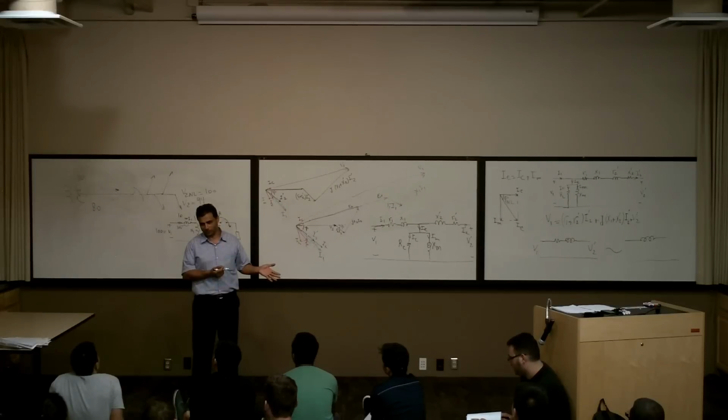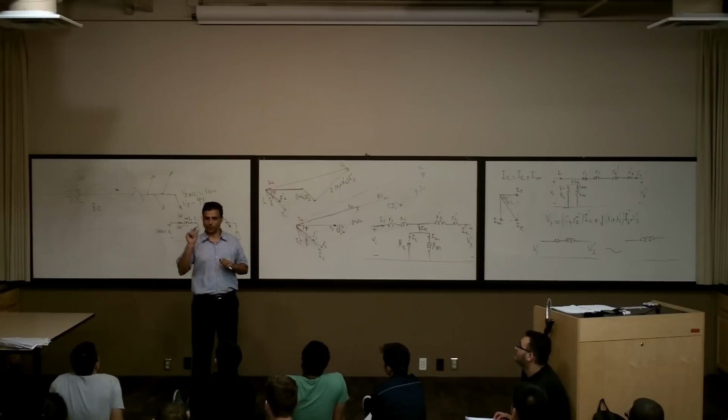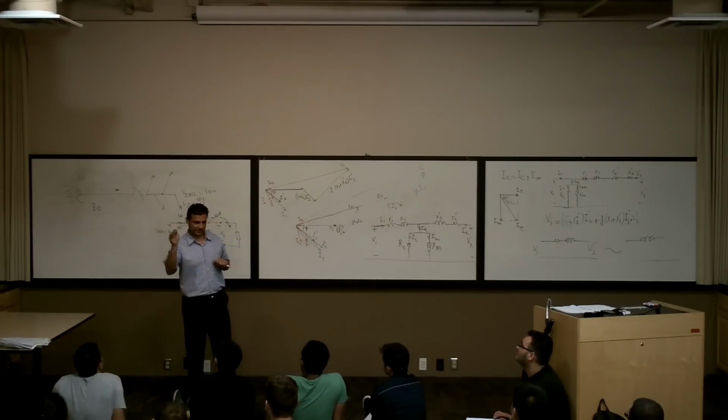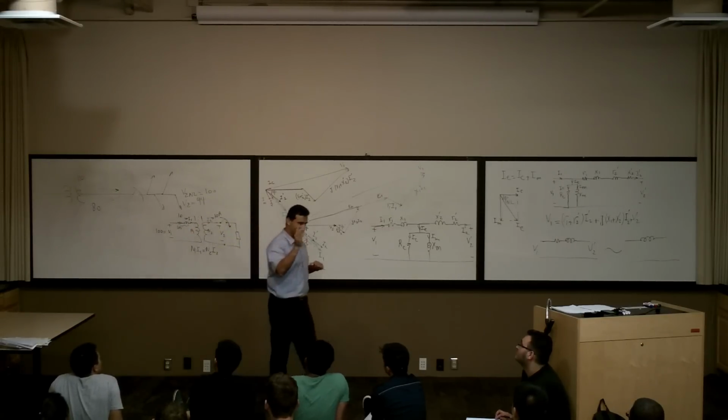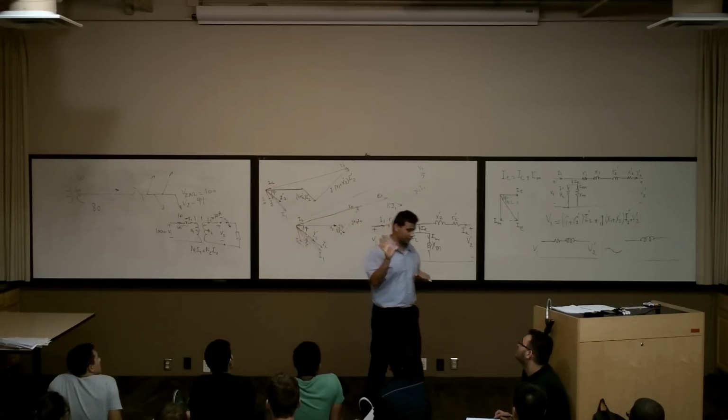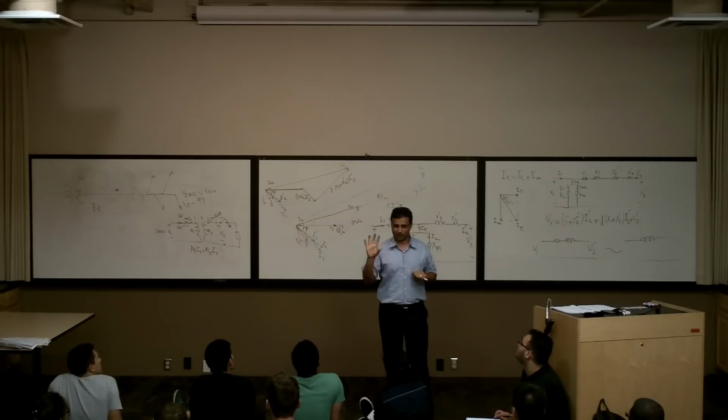What's the problem with 90 volts? You're happy with 90 volts? No, we can't power anything. Huh? It doesn't work. Everything's going down. It doesn't work, but it's also going to burn, for example, your electrical equipment, you know? If you look at all the electrical equipment, they say plus minus 5%, plus minus 10%. They say this is 110 volt, but it can work with it not being exactly 110. 110 is perfect, but it can work, for example, plus minus 10%.